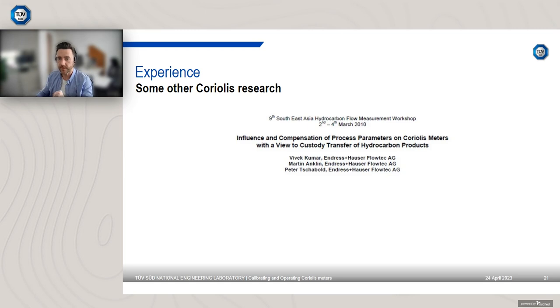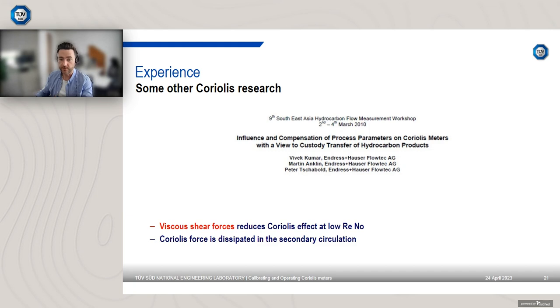Some other research, so from a meter manufacturer, in this case Endress+Hauser, they found that viscous shear forces reduce the Coriolis effect at low Reynolds number. So if you're operating at low Reynolds number, and you have this high viscosity fluid as well, or medium to high viscosity, say above 50 centipoise for relatively high viscosity to medium viscosity, the viscous shear forces start to reduce this Coriolis effect. So the Coriolis force is dissipated in the secondary circulation. This causes an underreading of the mass flow. So the effect becomes insignificant above a certain Reynolds number, but low Reynolds numbers, again, typically below 10,000 to 20,000, you find that there maybe is this effect of viscous shear forces reducing the Coriolis effect.